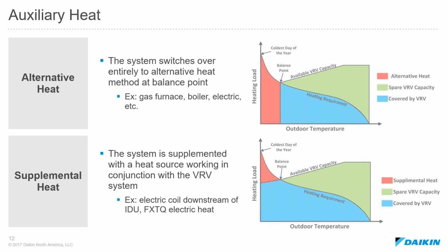furnace. The other option would be a supplemental heat source. So that's working in tandem with the heat pump. A good example of that would be the multi-position air handling unit, the FXTQ. So we have the ability to have that FXTQ continue to provide heat pump heating, and a supplemental source only come on and work in tandem with that unit when it's struggling to meet that set point.